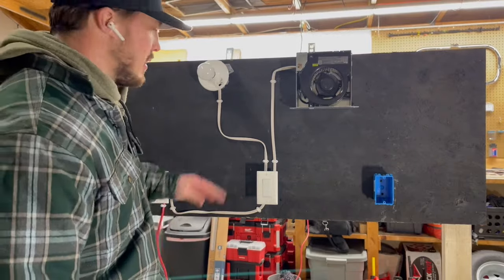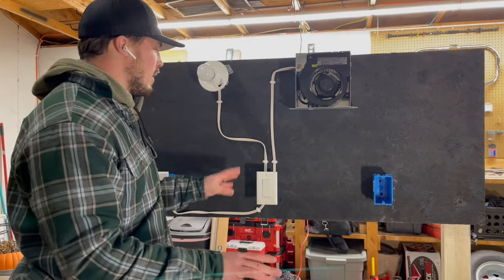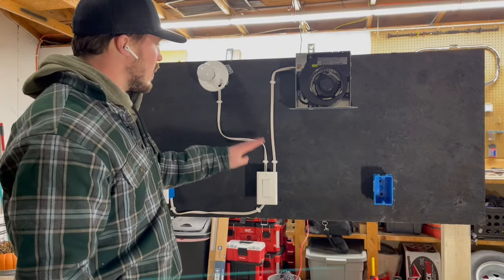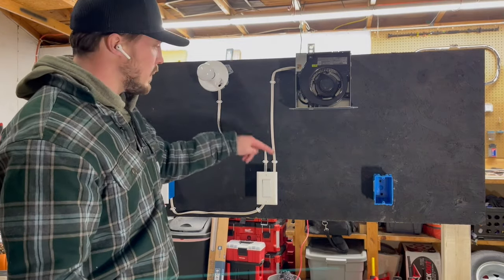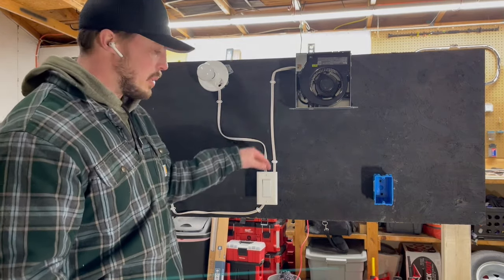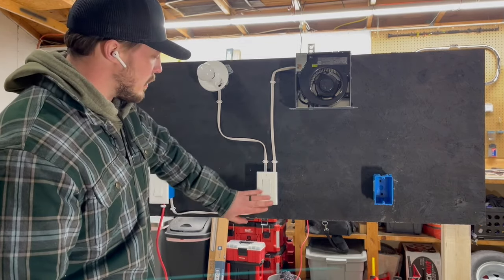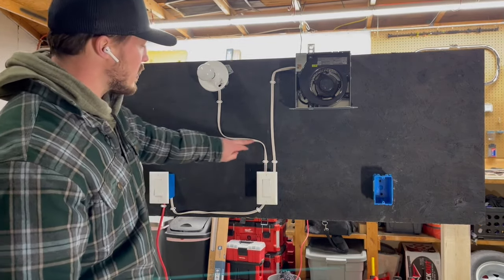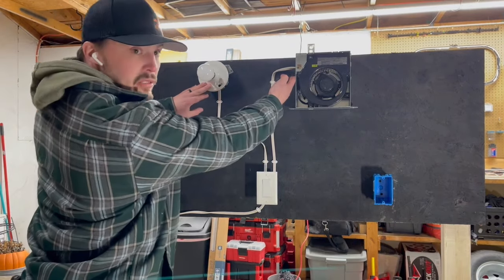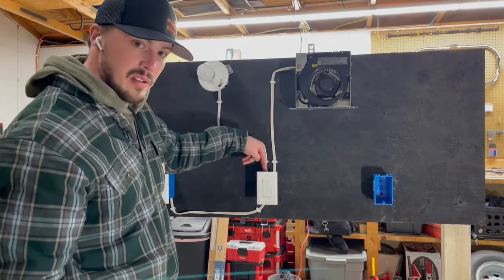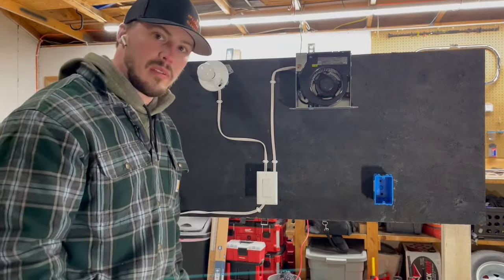I will say though the only way that this is gonna work in your bathroom is if both wires, your two switch legs, which is a wire that goes up to your light and the wire that goes to your fan, both come from your switch box. Now if they wired it to where your power comes into your switch and a switch leg comes up to a light and then they tap off this light into your fan and you only have one switch leg in your box, this is not gonna work.